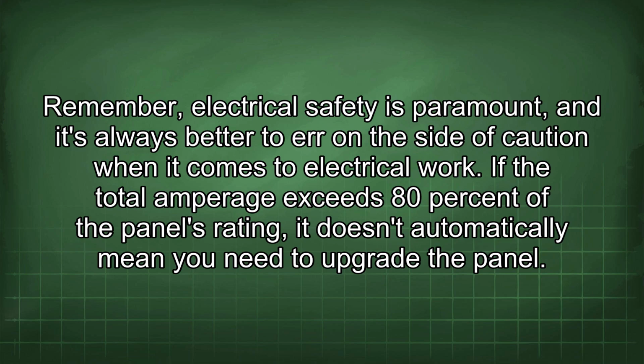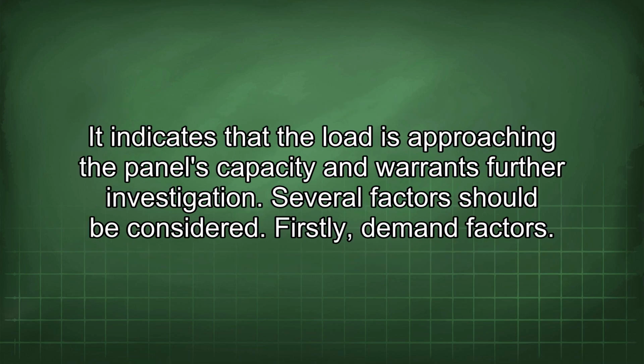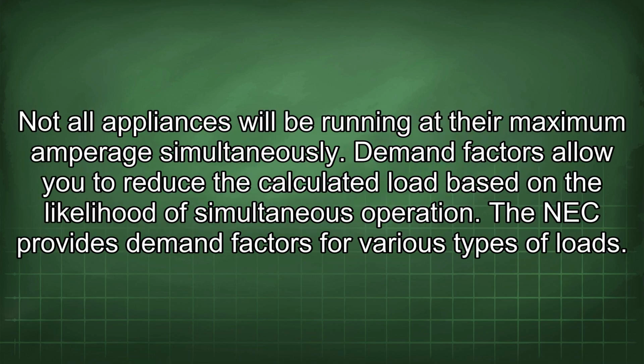If the total amperage exceeds 80% of the panel's rating, it doesn't automatically mean you need to upgrade the panel. It indicates that the load is approaching the panel's capacity and warrants further investigation. Several factors should be considered. Firstly, demand factors. Not all appliances will be running at their maximum amperage simultaneously. Demand factors allow you to reduce the calculated load based on the likelihood of simultaneous operation. The NEC provides demand factors for various types of loads.